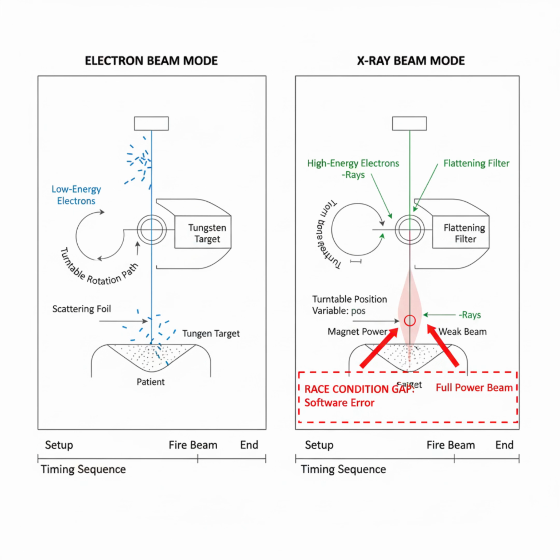The machine could operate in 2 modes. Electron beam mode, a relatively low-energy beam for treating surface tumors. The beam was scattered and shaped to spread the dose over a treatment area. X-ray mode, for deeper tumors. The electron beam struck a tungsten target, producing X-rays. A flattening filter spread these X-rays evenly across the treatment field.